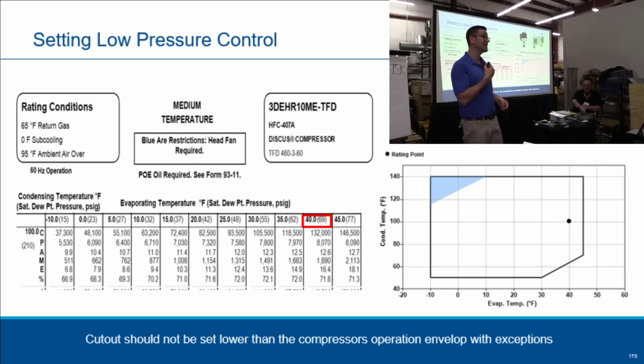Because I used to do that. I used to do that even before I came to Copeland. And I tell them about this and they're like, no, Trevor, that's not the way to do it. Do these different tests. Stay inside that operation envelope. So there's one scenario where you can run a compressor outside the envelope. So we make compressors down to minus 40 or even minus 10 here. Say you're running at minus 10 with this compressor. Well, to pump down, you have to go outside the envelope.